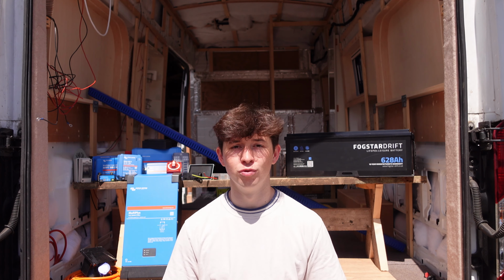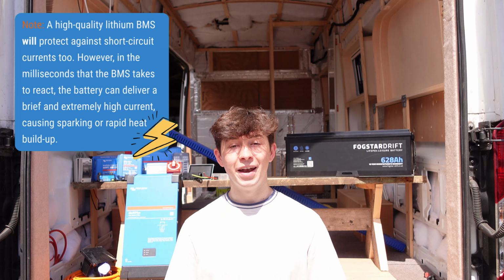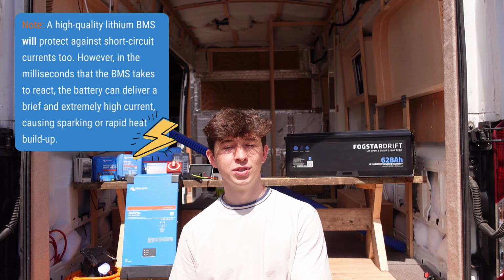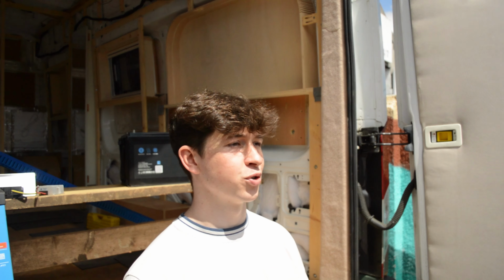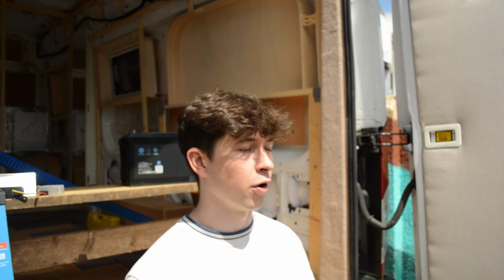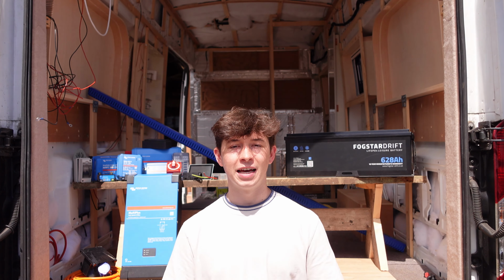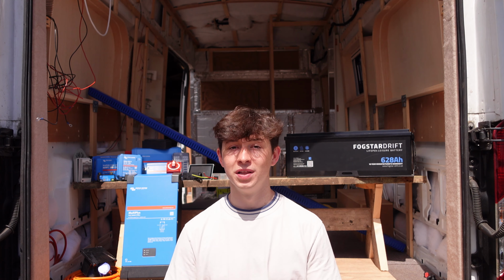Where a lithium battery does demand respect is with regard to short circuit currents. Imagine if you put a spanner between the two terminals of a lithium battery. The low resistance circuit that you've created could send over 1,000 amps through the short. An AGM battery would also still be dangerous in this case, but the internal battery chemistry and voltage lag means that the current is more limited. Again, in either case, the risk is mitigated in a properly designed system.